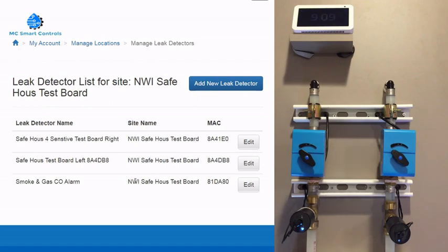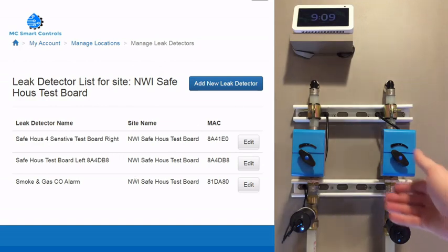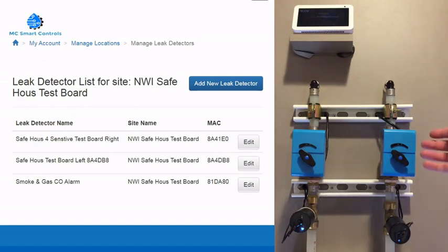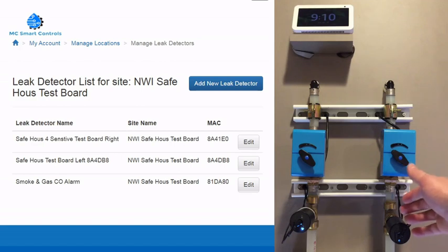Moving on to the condo services, the Safe House flow sensors, as shown here, can be installed on both hot and cold water services. When the flow sensor detects water moving in the pipe according to the user's set parameters, the ball valve is closed and an alert is sent by email or SMS. The Safe House flow sensor has a built-in PCB with a direct user interface so that the homeowner can set the flow.